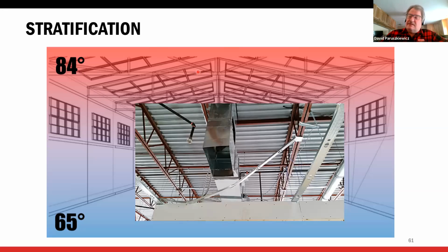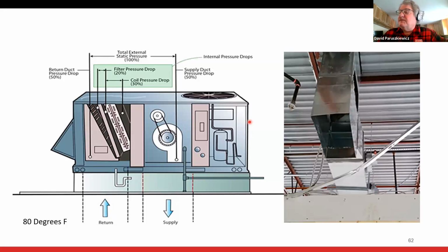And so even though the space isn't up to temperature, I start getting all this warm air accumulating up above and it hits that return, and we start tripping the limit. So that's something we really have to look for when we're tripping a limit. Stratification: do we have a duct system that's allowing all this heat to build up above? Especially when we've got a very limited drop for my return like this. It drops up in the joist. That's a perfect place for air stratification and tripping limit. So again, put that in your book. If you're getting 80 degree return air, you're going to cycle on a limit.